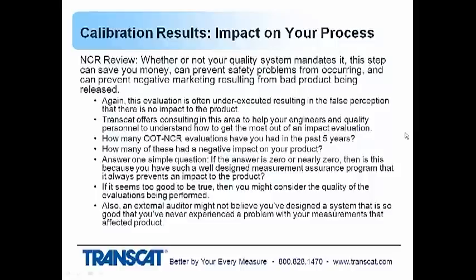The evaluation is often under-executed from my perspective and my experience, resulting in a false perception that there's no impact to the product. If these NCR reviews are not thorough enough, or not making the right comparisons of the out-of-tolerance data to your decisions, or not capturing all of the areas where the instrument was being used, that's often a problem. Then you're effectively breaking the traceability chain or breaking the measurement assurance process for your product.